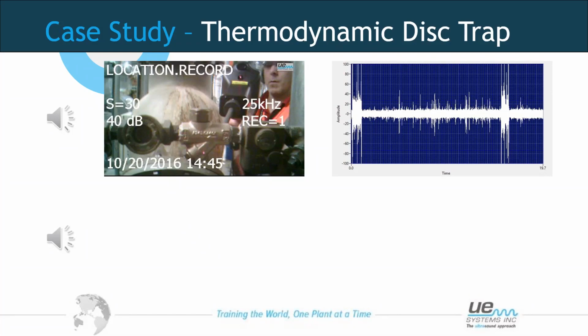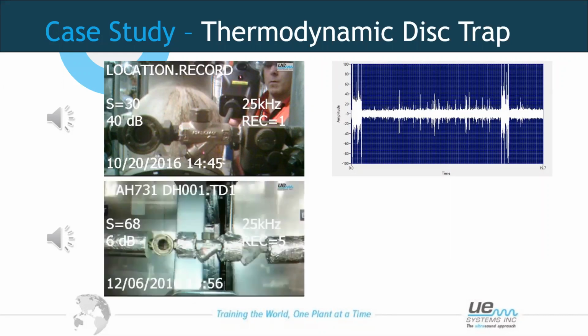So what we can see here from the sound recording is 2 increases in turbulence, and we can hear the clear opening and closing of the steam trap, which indicates to me a good steam trap. This is a good example of a trap. Now, on this site, there were lots of these traps, so we were able to go around and compare them to this good sound recording to understand the condition. So we came across another one, and we took another sound recording to do an inspection, and this is what we came across.